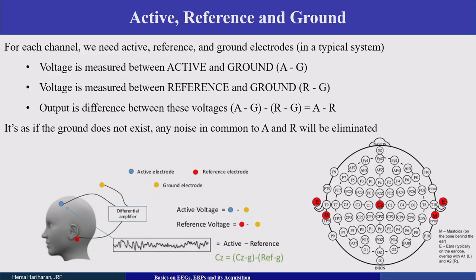The EEG recording is obtained by measuring the voltage between the active and ground electrodes, then the voltage between the reference and ground electrodes. The potential difference between the active and reference gives the EEG recording. The reference and ground are typically placed at the ear lobes or mastoid. Some caps have their own built-in ground and reference positions.